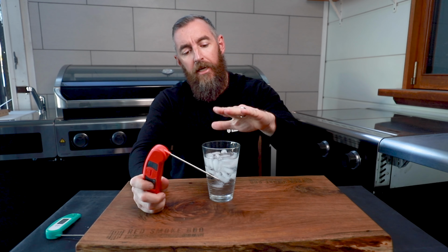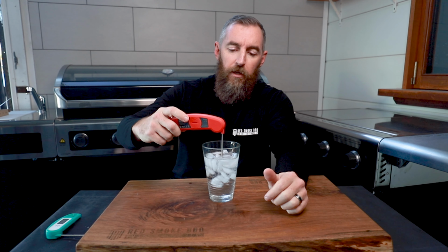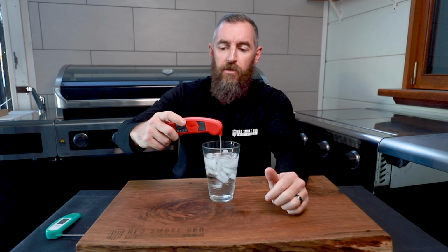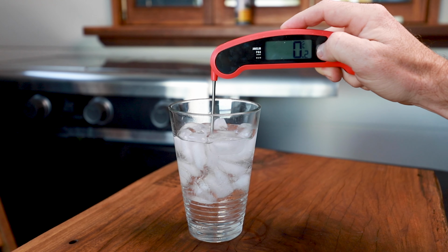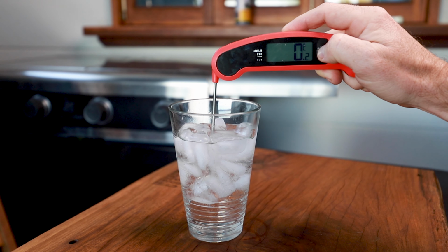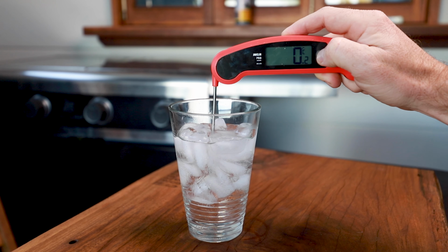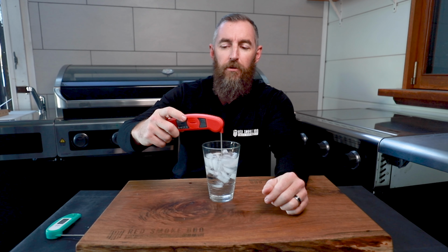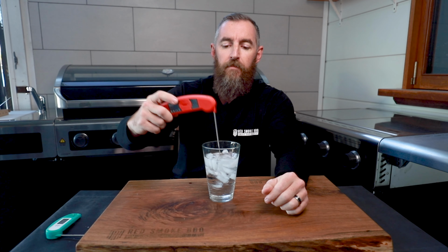Okay, so in the manual for the Pro, it talks about doing an accuracy test for your thermometer. And to do that, you take a glass of water, fill it with ice, stick the probe into the middle of the glass, hold it there for a few seconds, and you should get a temperature reading of within 0.5 of 0 degrees. Now the Pro's come in here around about 0.2, 0.3, which is well within the guide of 0 degrees, so I'm happy with that.